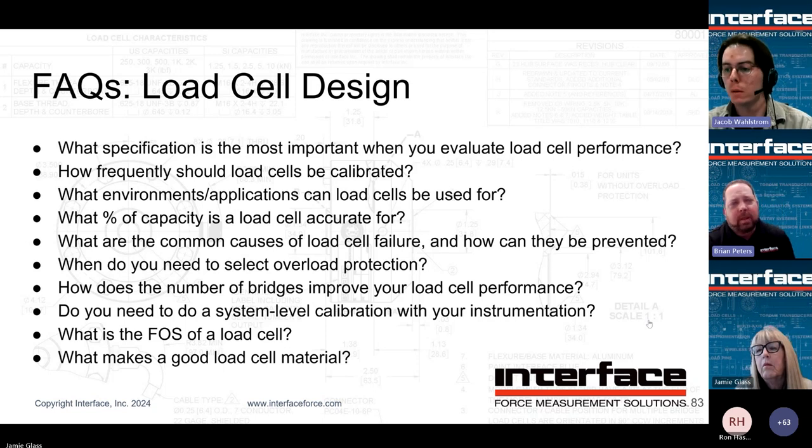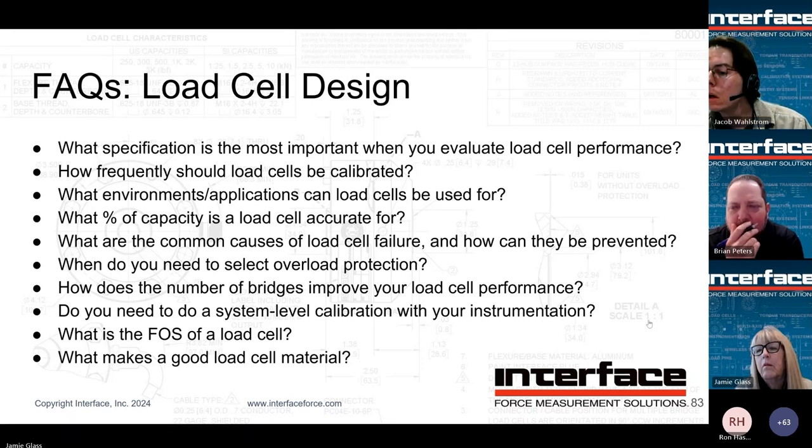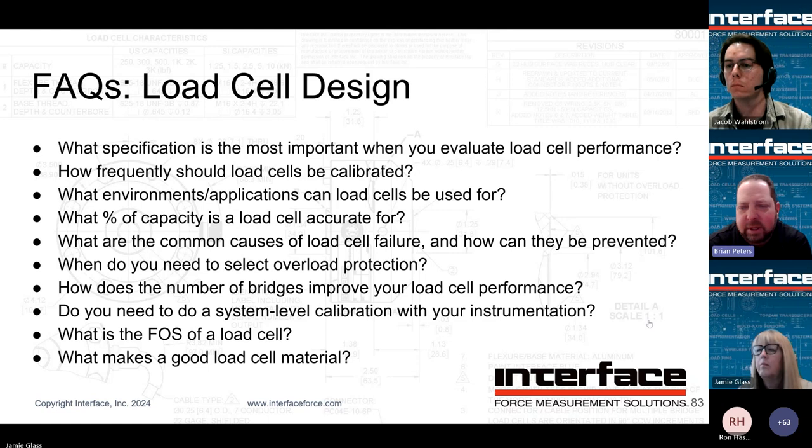True. Also, most of our standard product temperature range is up to 200 degrees, so up to 170 should be okay. Jaime, let's circle back after this. I'd like to know the model and get some more information, and we'll try to run that to ground. But no, it shouldn't be changing if it's within the operating range.